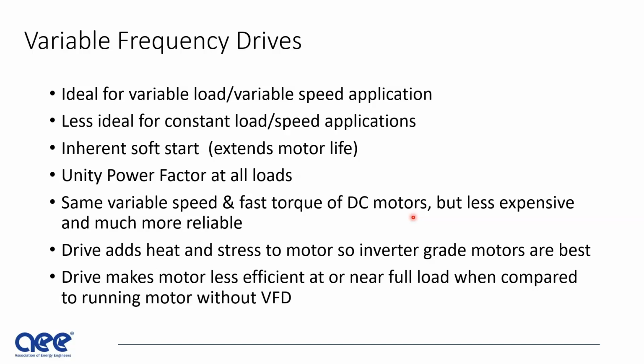I'm working with a customer now. It's got 7 400 horsepower motors, and they want a generator to run the motors for backup, and the generator company is misspecifying the load on the generator that it can take because they're ignoring the fact that VFDs are being used and they offer a soft start feature.